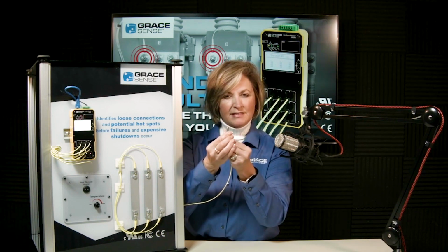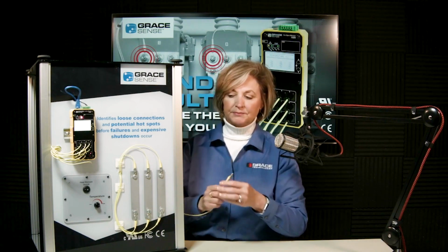So the benefit to that is actually the fact that everything is cured inside this probe tip, and it's not necessary to ever have to calibrate it or do any kind of adjustments to it once it's installed. So for OEMs, they can pot over it, we can insulate on top of it, and you're still going to get a really good reading from that location.